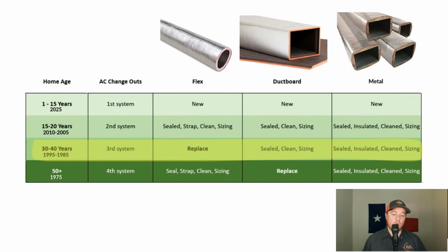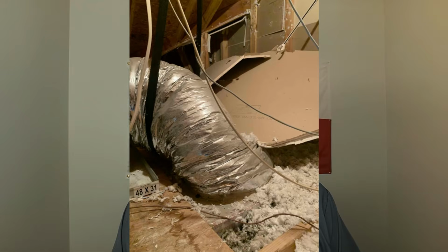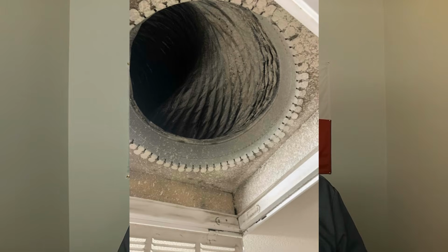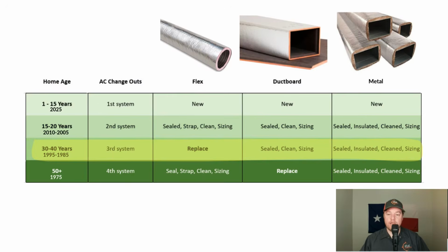However, is it completely required to replace it at this time frame? No, I've seen ductwork last much longer than this. However, in this time frame, it's just a good rule of thumb, because it could be starting to fall apart. It's not going to be as efficient as it used to be. It could have been stepped on, spliced into, or cut into. It could also be filthy inside, and so on. Now, when it comes to ductboard, you should be able to get one more change out without having to replace the ductwork. And once again, you're going to want to make sure everything's sized right.